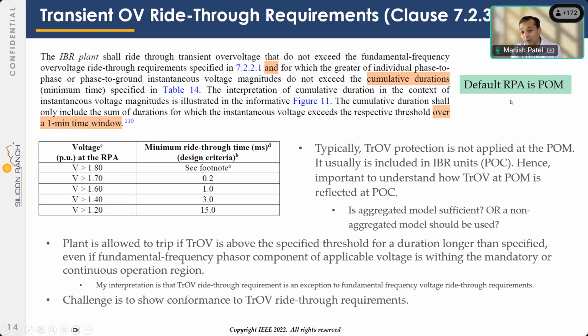Second, I mentioned this already, the requirements apply at the point of measurement. Typically, there is no transient voltage protection at the POM. That kind of protection belongs in the controls of IBR units. So one has to understand how to reflect any transient that appears at the POM of this magnitude for this duration, and how it would appear at the POC. Do we do this analysis using aggregated models? Do we do this using non-aggregated models?